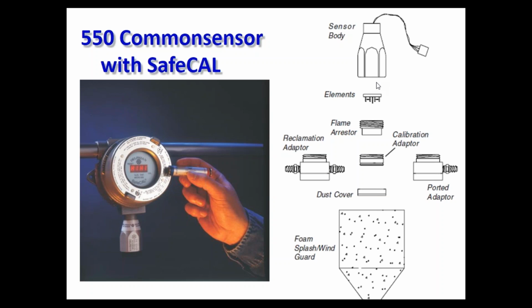When it burnt out, you used to have to replace the whole sensor. Now we can sell you what we call an SB, an element sensor bead, in a replacement PC board that plugs into the sensor. So you remove the flame arrestor, you plug in a new element, you do a quick coating resistor on the back of the sensor. That's the setup to make sure that it's running at its proper operating temperature.